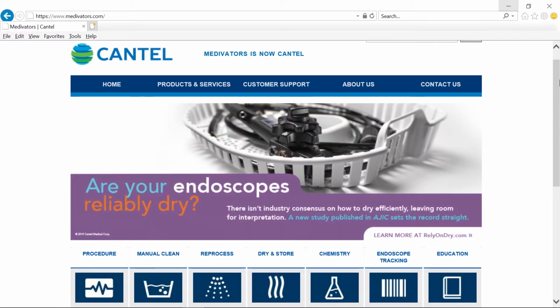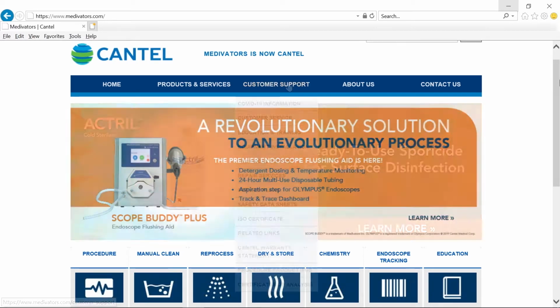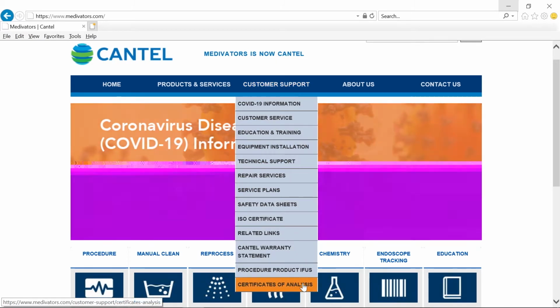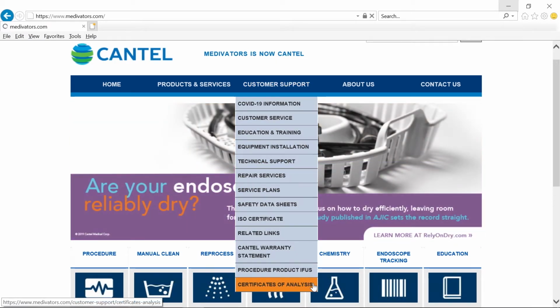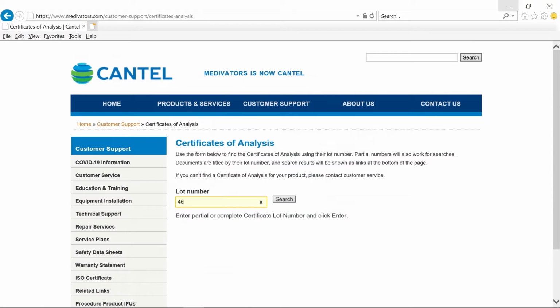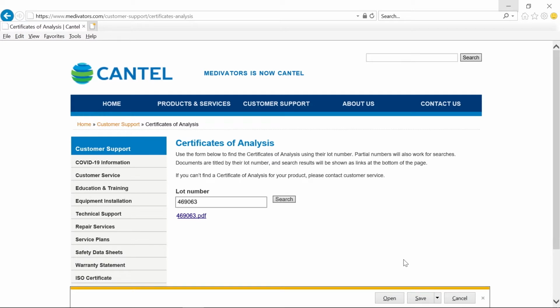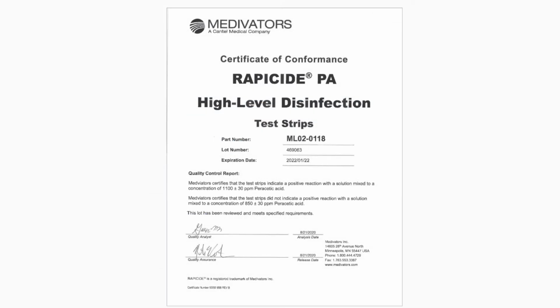To locate the certificate of analysis, go to www.medivators.com. Click on Customer Support. Click on Certificates of Analysis, and a new window opens. Enter the lot number from the side of the Rapicide PA test strip bottle. Click Search. Click the PDF link that appears under the search bar to access the Certificate of Analysis. Print off the Certificate of Analysis that states the quality control for that lot number was performed by Cantel. There is no need to perform additional quality control.